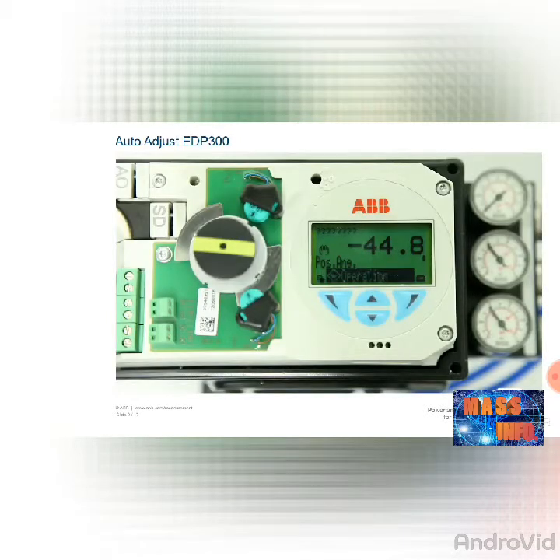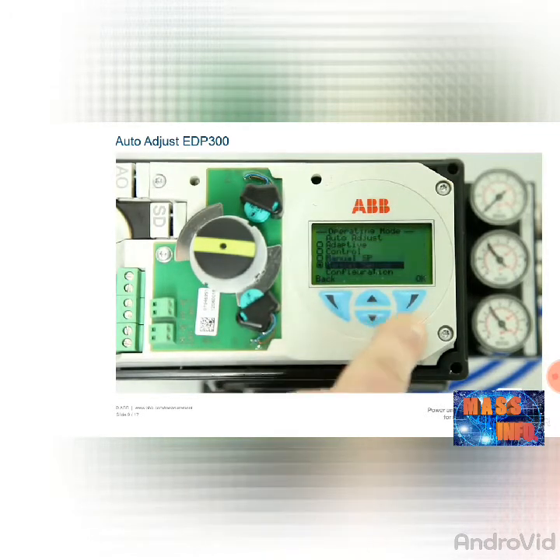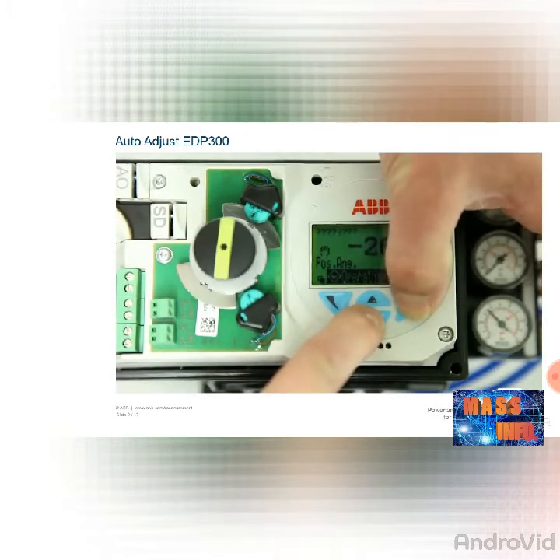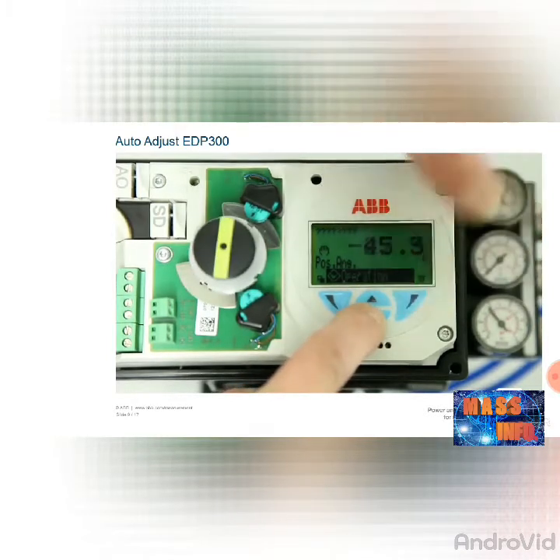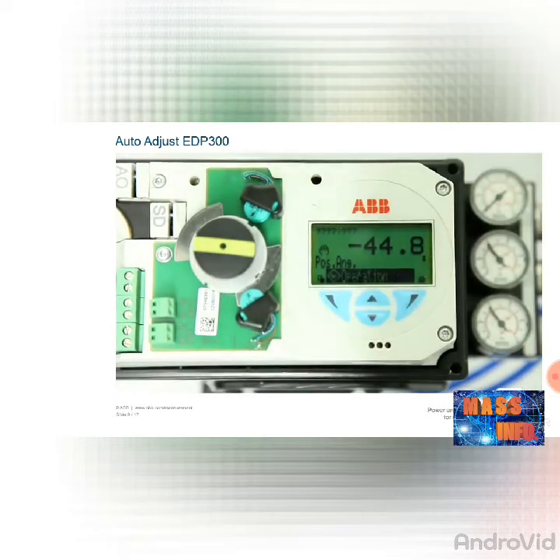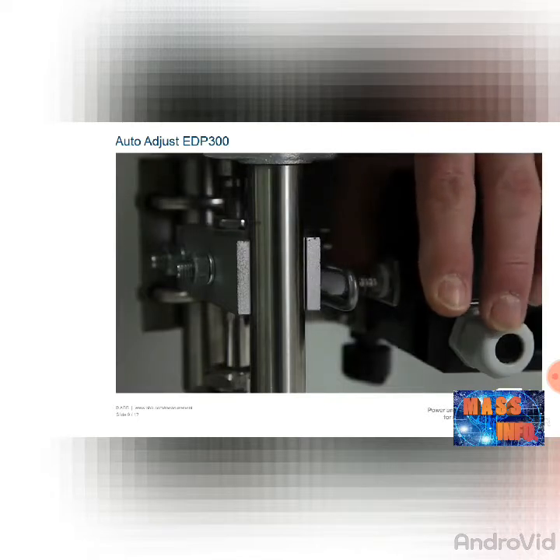The auto-adjust function for the EDP-300 works in the same way as for the TZIDC. The only difference is in the operation via the menu. Now check the two end stops of the actuator. Call up the menu by pressing the right-hand button. Use the arrow buttons to select the manual SP option and confirm it with the right-hand button OK. By pressing the top and bottom arrow buttons, you can approach both end positions and check them. For a linear actuator, the values displayed should be between plus 30 and minus 30 degrees, and for a rotating actuator, between plus 45 and minus 45 degrees with a minimum angle of 25 degrees and run parallel. If this is not the case, please correct the mechanical setup as described in the mechanical connection linear chapter.